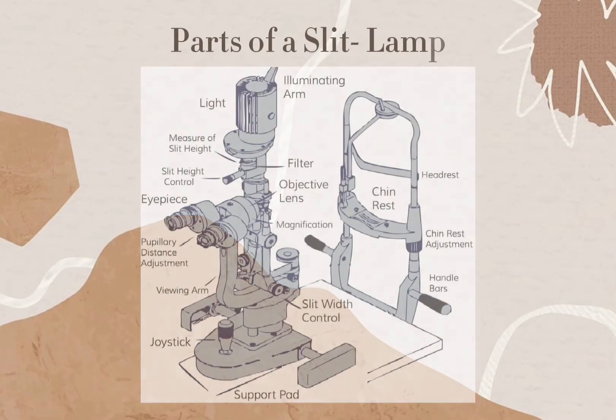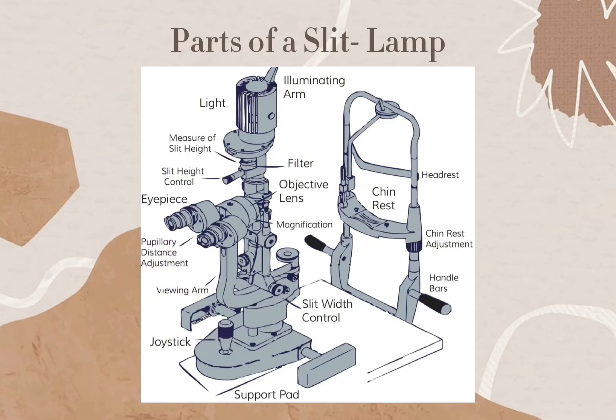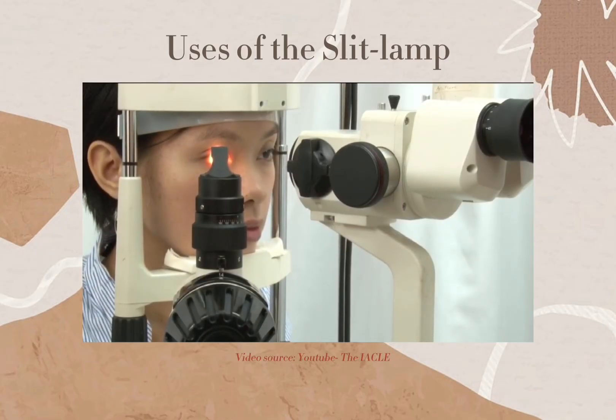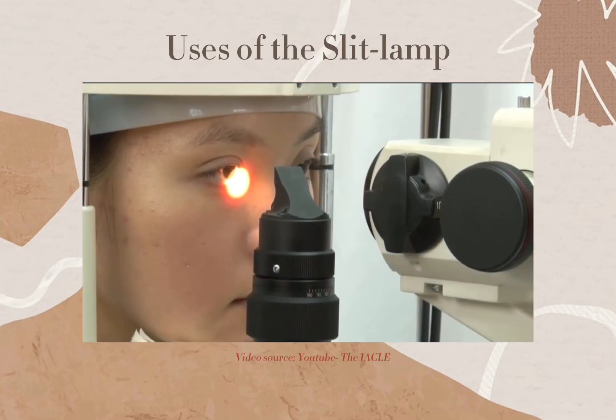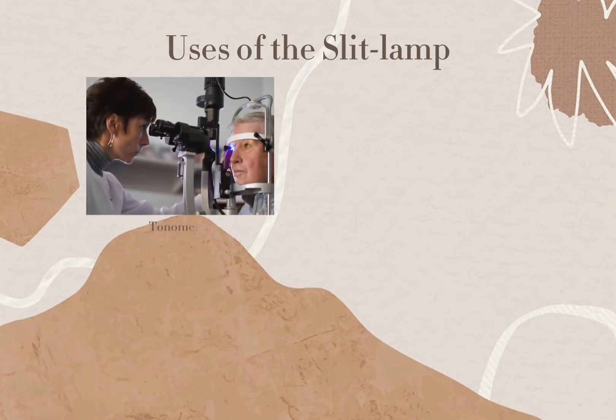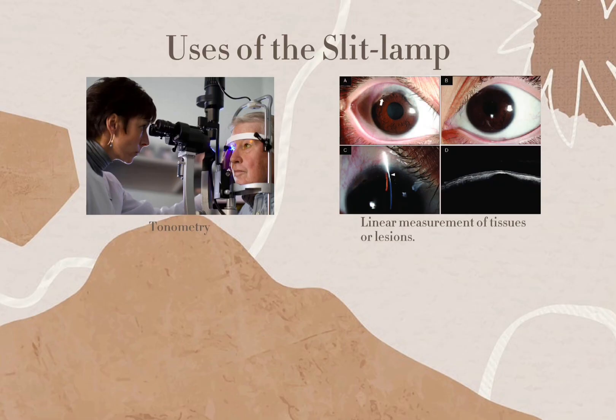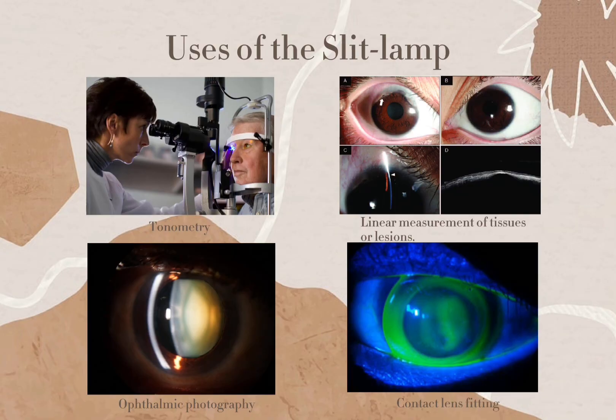The last part of the eye exam is the slit lamp biomicroscopy. The slit lamp biomicroscope consists of three principal portions: the viewing arm containing the eyepiece and objective lens, the illumination arm containing the light source and its controls, and the patient positioning frame containing the headrest, chinrest, and handlebars. The slit lamp is indispensable for detailed examination of virtually all tissues of the eye, routinely used for the anterior segment, including the anterior vitreous. It is also used for tonometry, linear measurement of tissues or lesions, ophthalmic photography, and contact lens fitting. That concludes the eight-part eye exam. Thank you for watching.